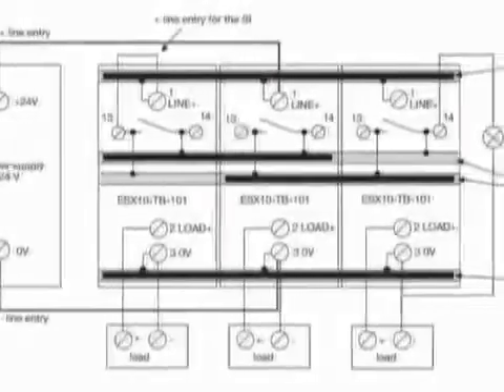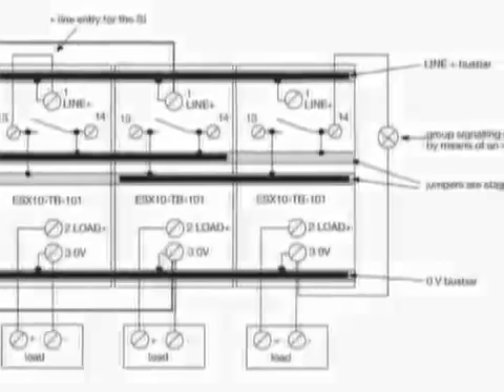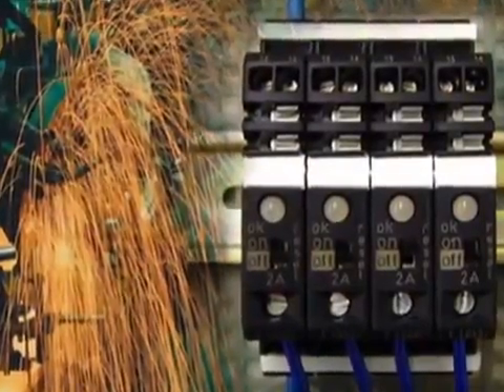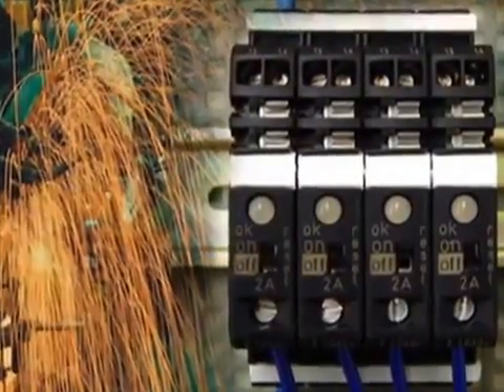The major benefits to this are selective disconnection of faulty loads, which reduce equipment downtime, ease of troubleshooting 24-volt DC circuits, and keeping the integrity of the 24-volt DC system.